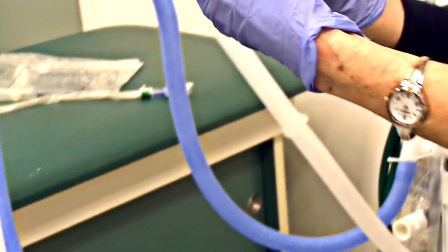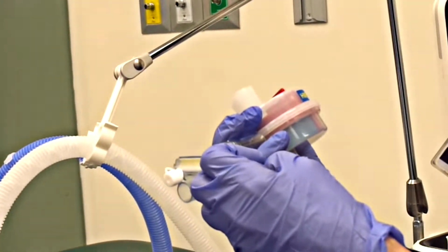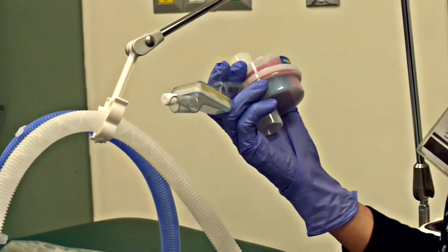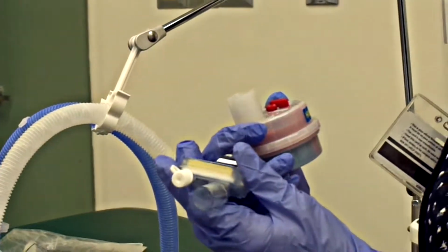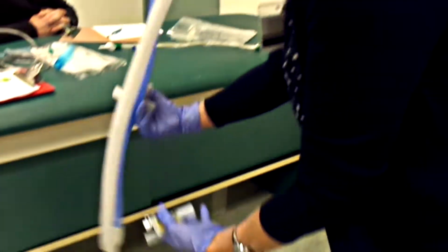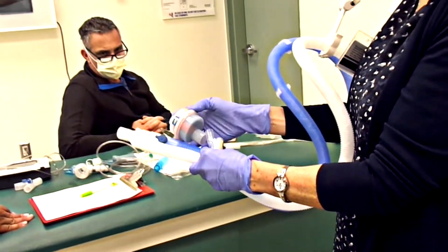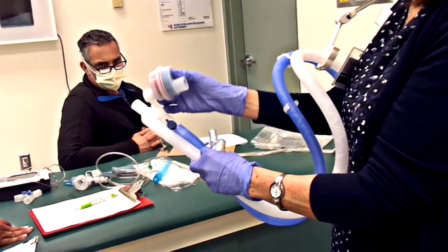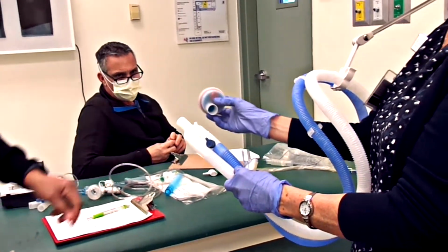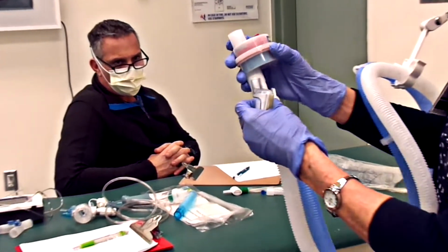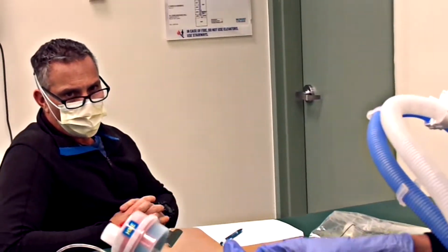All right, so when you're placing the HME in line, it has to get exhaled air so it can trap the heat and moisture, and it needs to get inhaled air so it can re-deliver it to the patient. So should we put it on the inspiratory side, the expiratory side, or on the Y? On the Y. Yes, very good. So it goes on the Y. And we'll use this one for now. Now that's not orientation dependent, right? That can be any which way you want to. Yes.